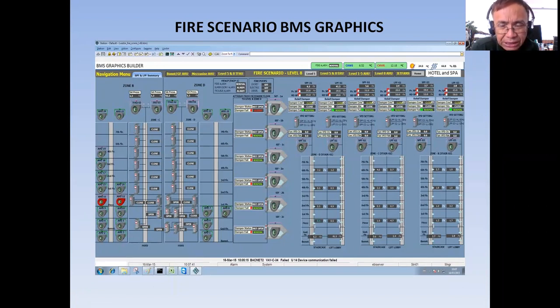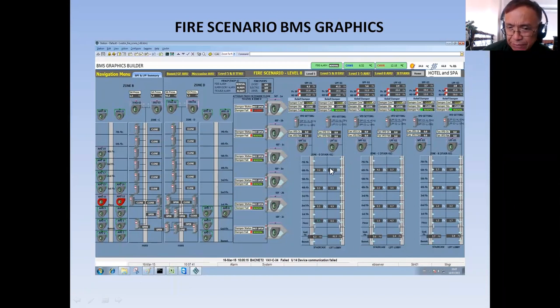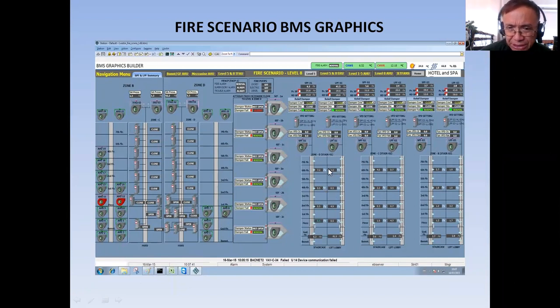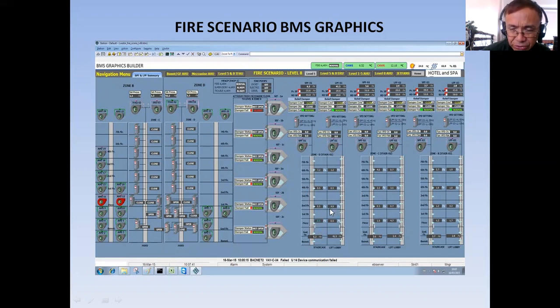In this graphics, I have put all the HVAC equipment related to the fire scenario, like staircase pressurization. I have three staircases, and I had two fans related to each — one staircase pressurization fan and one lift lobby pressurization fan. Inside the staircase and lift lobby, we are installing a differential pressure sensor to give us the actual pressure reading inside the staircase and inside the lift lobby.